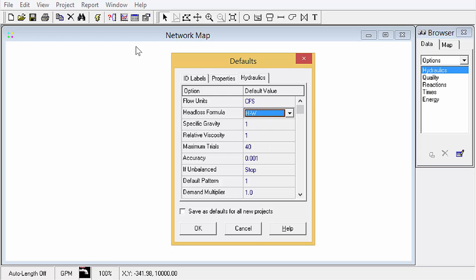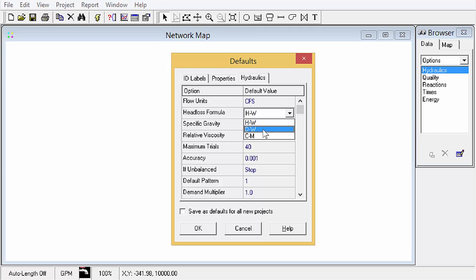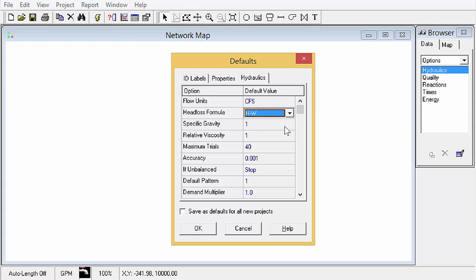You can choose from three options for head loss formula: Hazen-Williams, Darcy-Weisbach, Chezy-Manning. Typically in the water industry we're using Hazen-Williams, and specific gravity, relative viscosity, those things are usually left at the default.